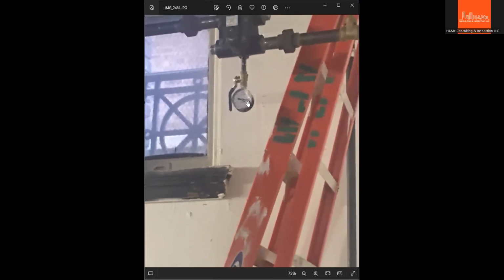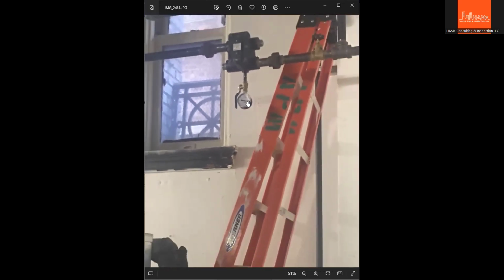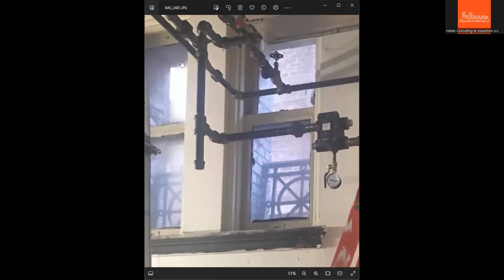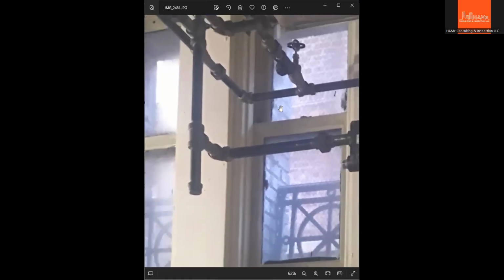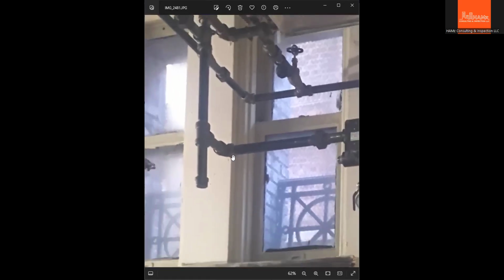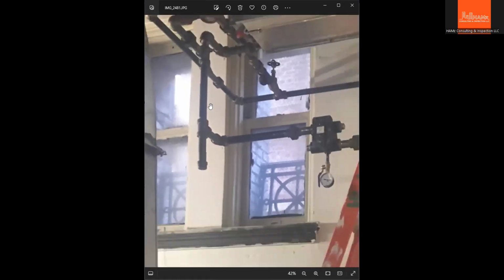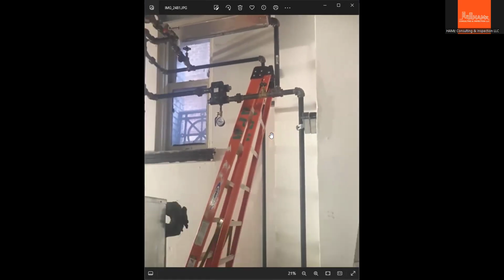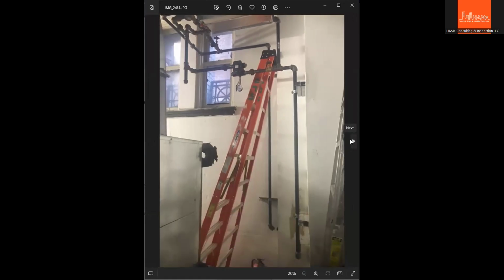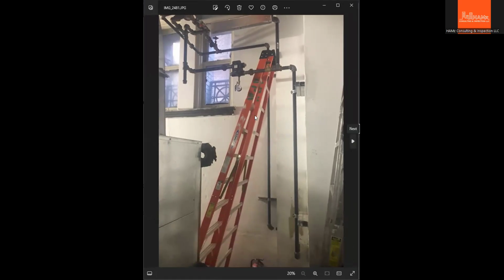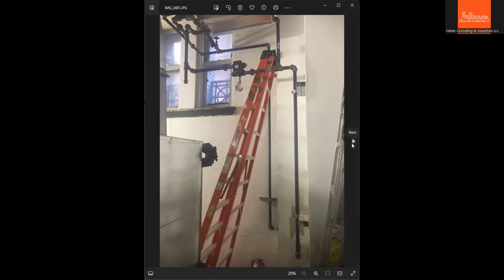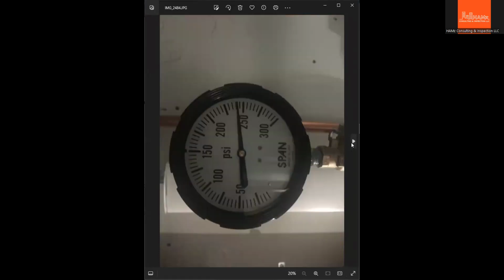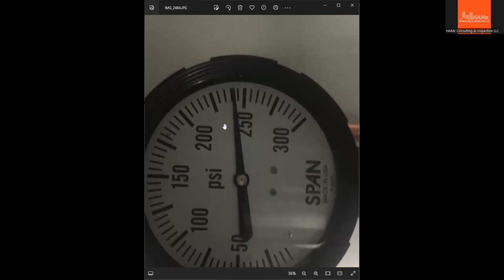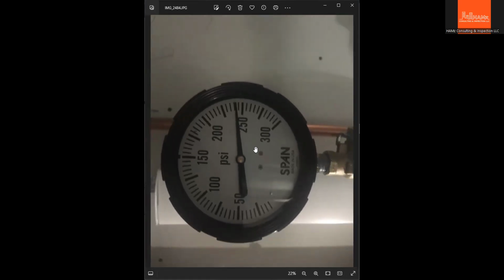We're going to discuss the required pressure for each particular piping system. During the test, you need to visually verify that all joint connections are totally leak-free. There are no drips of water and no bubbles of water outside of the pipe surfaces. During inspection, take a photo of the whole assembly where you have taken the test setup and the pressure gauge. This is how you're going to know what the test pressure is.